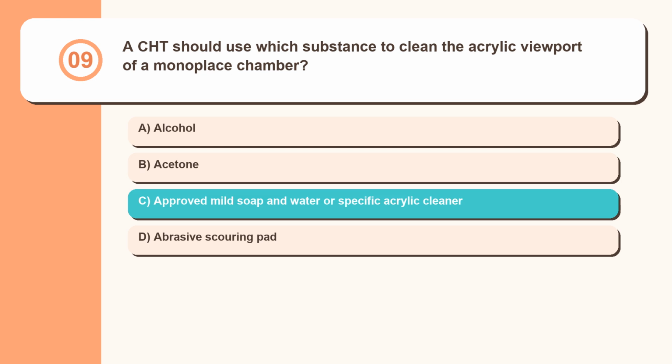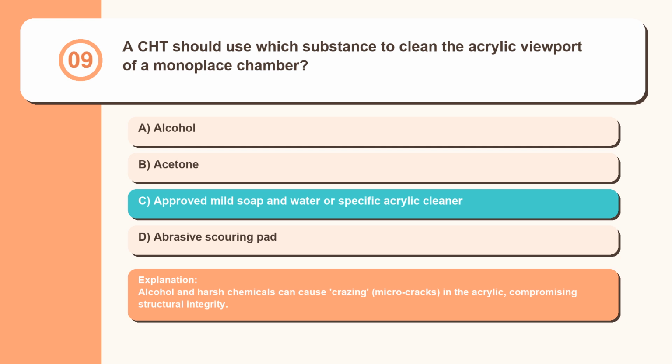Question 9. A CHT should use which substance to clean the acrylic viewport of a monoplace chamber? Alcohol, acetone, approved mild soap and water or specific acrylic cleaner, abrasive scouring pad. Alcohol and harsh chemicals can cause crazing, microcracks in the acrylic, compromising structural integrity.